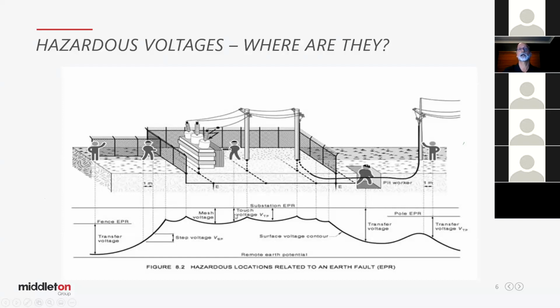Indeed, here is an indication of a touch voltage that this worker could be exposed to during an earth fault. If he's touching a conductive surface there, and the soil, his hand may be at a different voltage than his feet. We've got a fellow outside the fence here, and he's got his feet in contact with the ground. Due to the voltage gradient, there's a different voltage from one foot to the other, and therefore there'll be a current going from one of his legs to the other leg. Part of that will go up and past his heart.